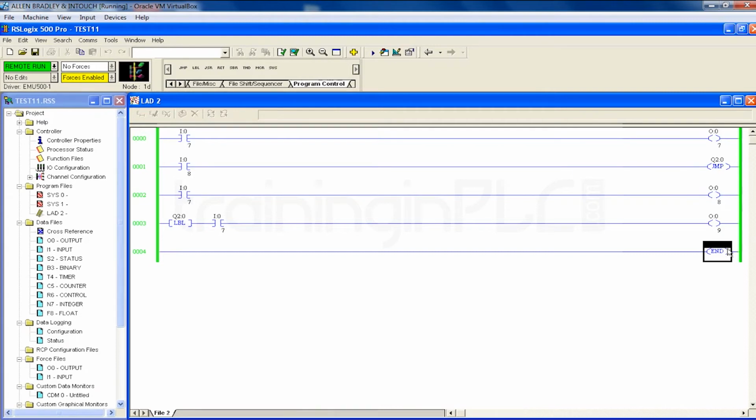So the rung limit is set by this label. This label I have introduced at the beginning of rung 3, so it will be taking before that. From here to here it is skipping. You can include 2 more rungs also here, no issues. So this is how you need to use the jump instruction.